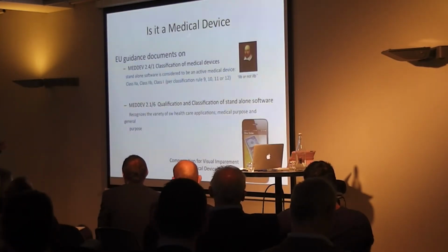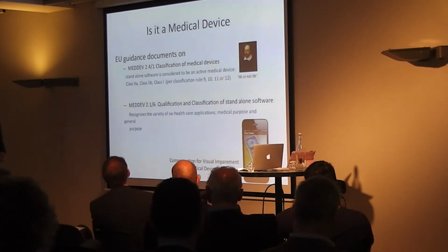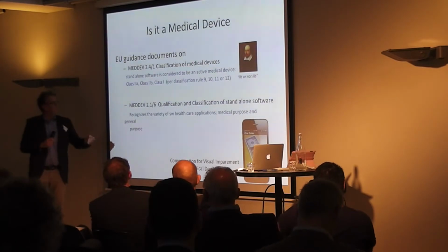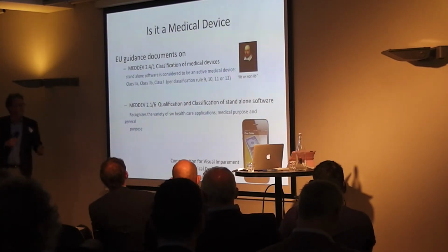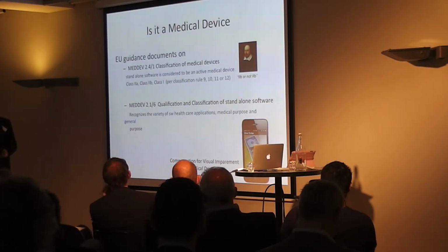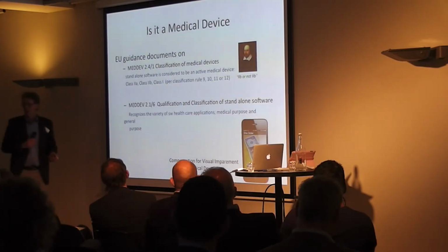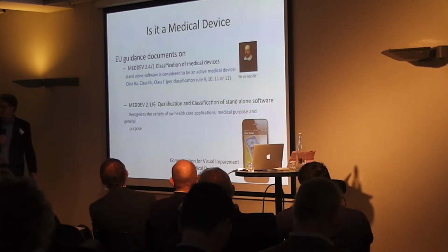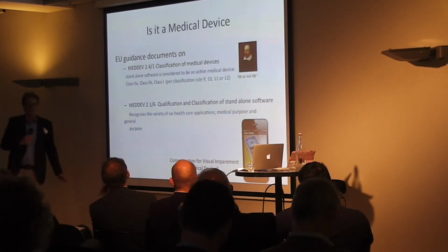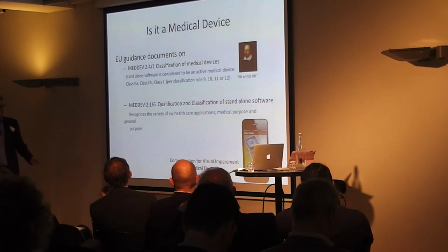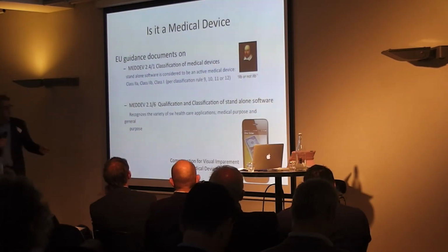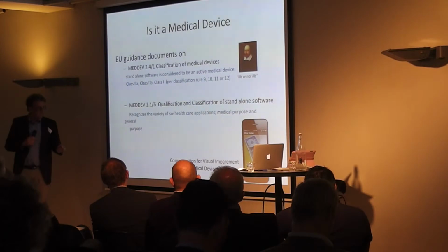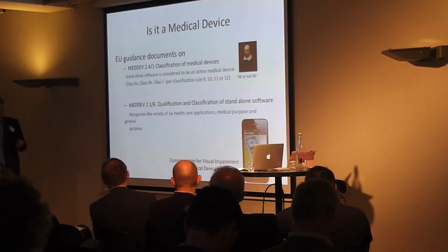Okay, so the classification is something you need to take into account. Basically, it's ticking off the classification rules of the directive and ends up in class 1, 2A or 2B. Many of the apps are in class 1. For some of the apps which claim class 1, it is doubtful whether they actually are class 1 and whether they actually are classified as a medical device. That's the current gray area. Some devices, and I think the VISNet will be even the first, is a class 2A medical device. And then you also have the specific devices Eric discussed, the classification for standalone software.